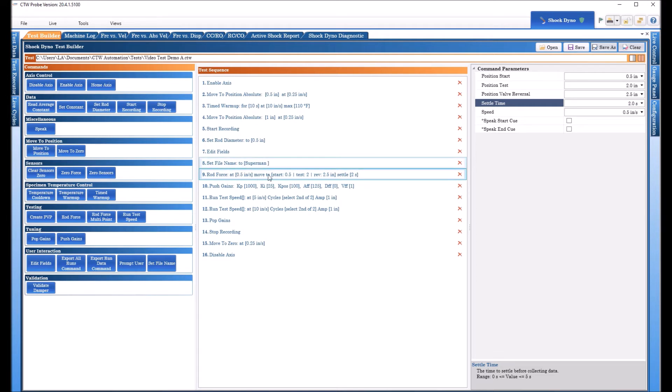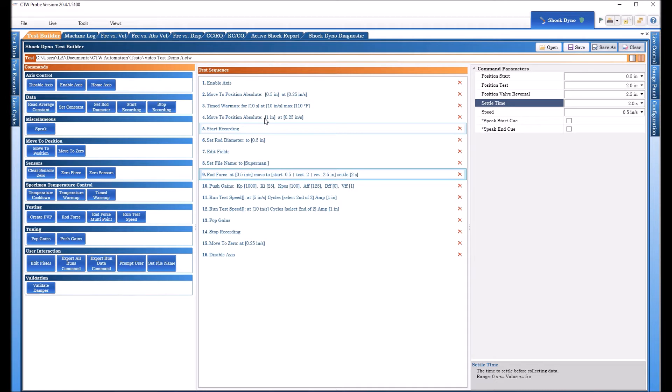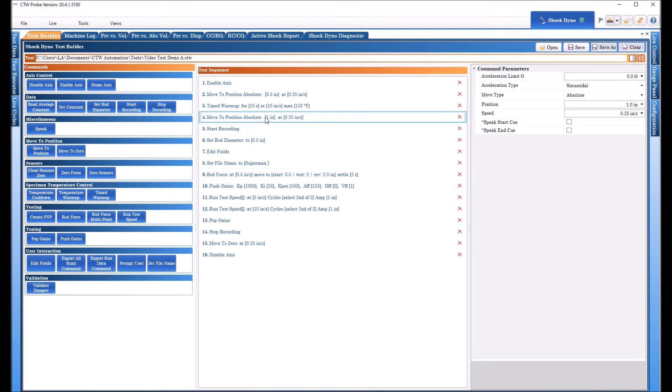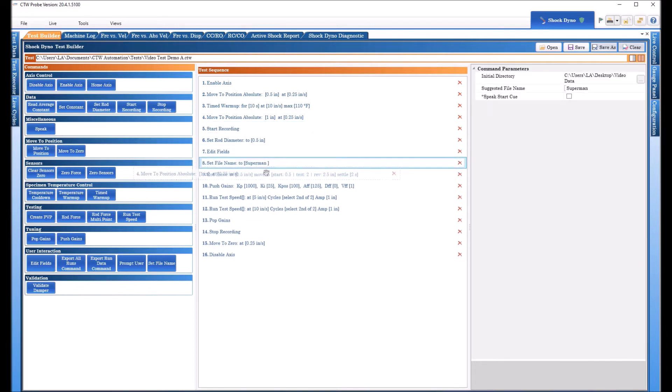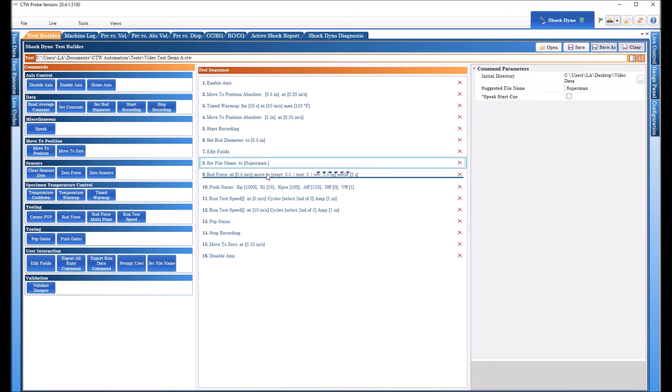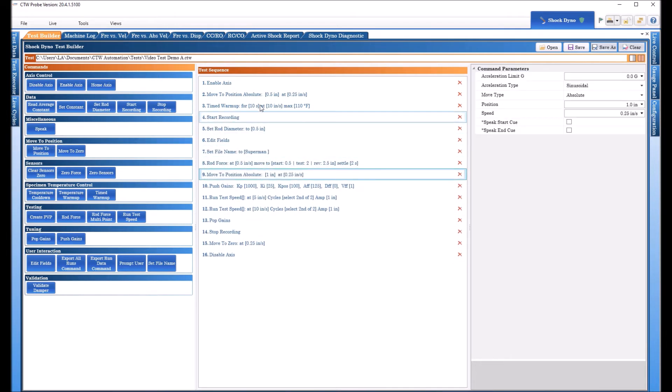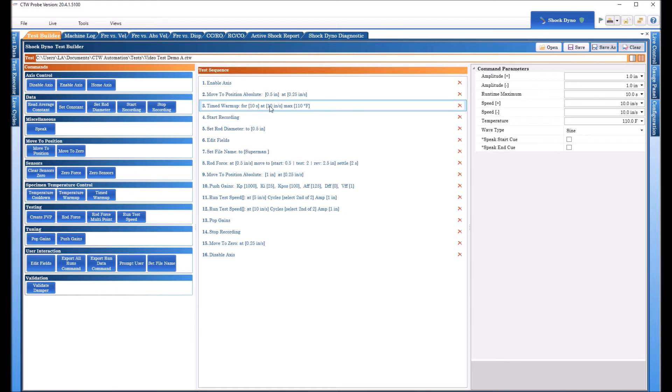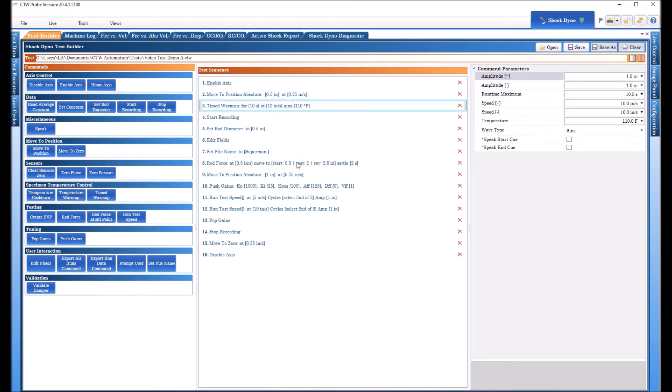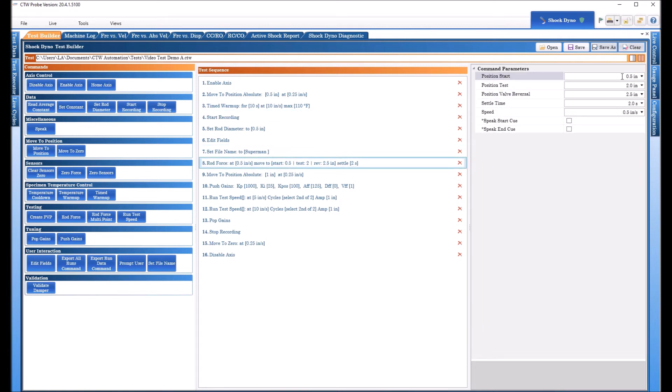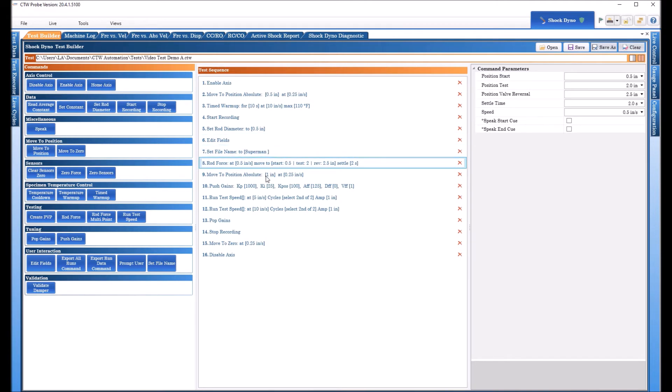Now after the rod force we want to make sure the actuator goes to where we want to begin our tests. So I'm going to take this one and move it down to right after rod force. Now I was able to move it because after the timed warm-up regardless of where the damper is at that point this rod force is going to set where it's going to start so it's going to end time warm up and it's going to go to this half an inch per second and then the rod force is going to happen.